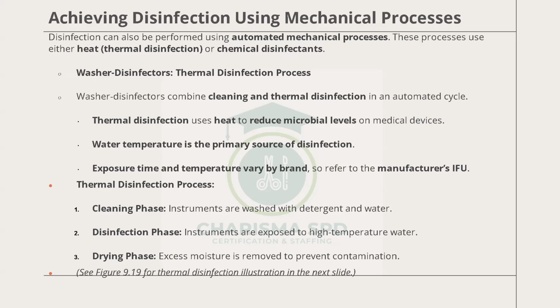The cleaning phase, the disinfection phase, the drying phase. Yes, so we have the cleaning phase and the drying phase. These washers have the cleaning phase when you put in the instrument. The first stage normally is called the wetting stage, where cold water is injected through the arms onto the instrument. The reason is to avoid what we call coagulation, where fat hardens. Then the next stage is the washing stage itself, the clean stage, where enzymatic detergent formulated with amylase, lipase, and protease comes in.